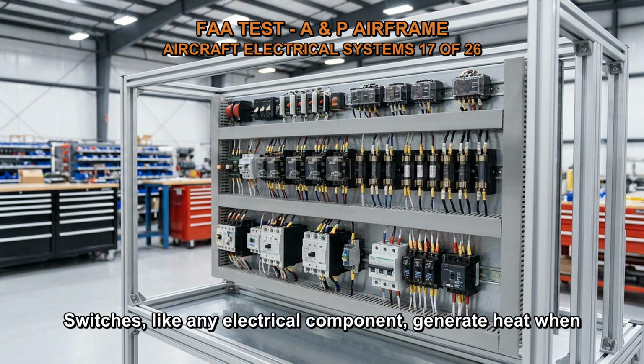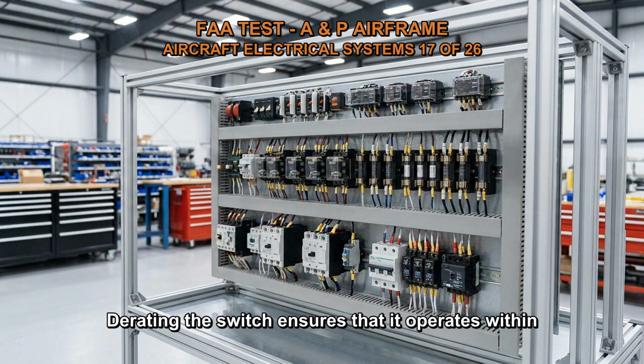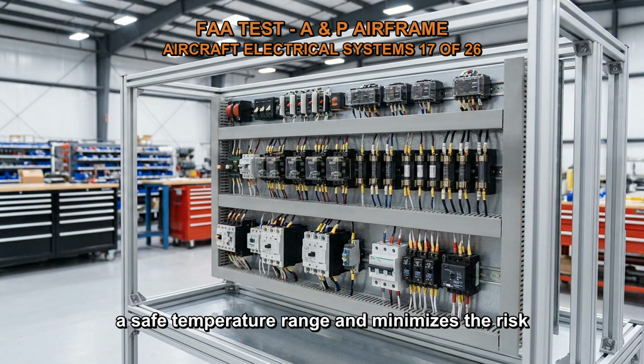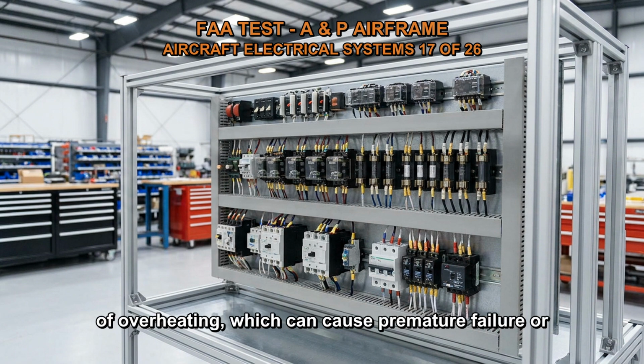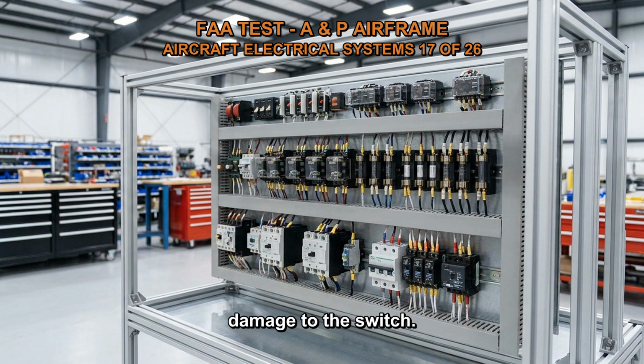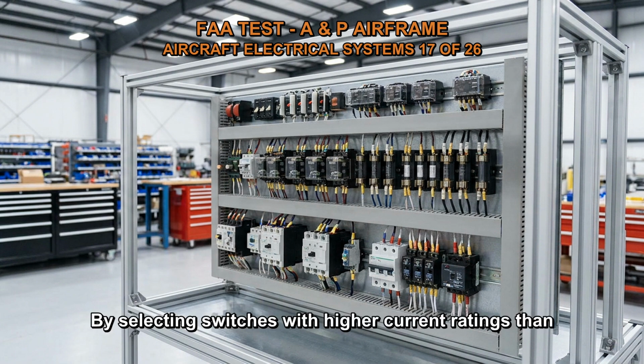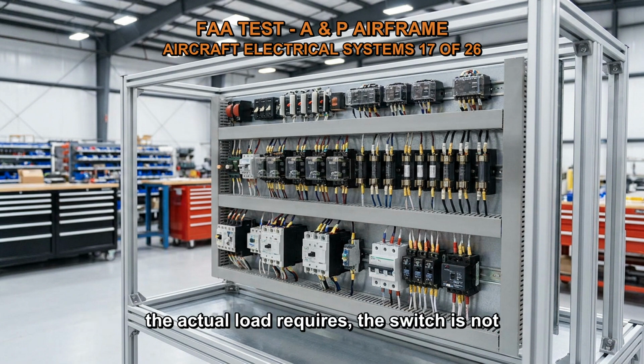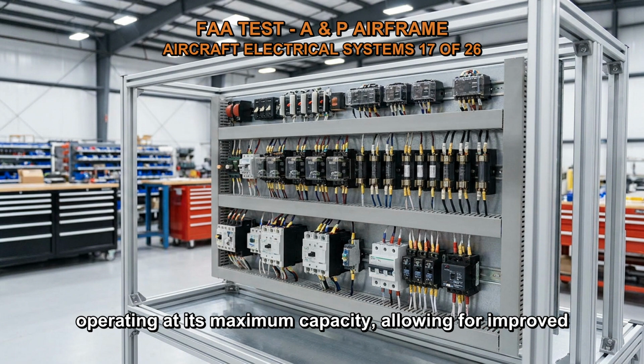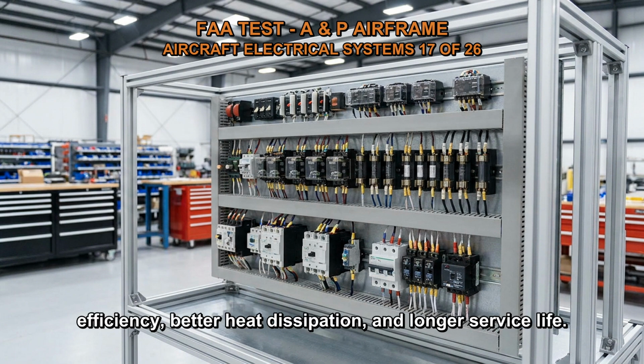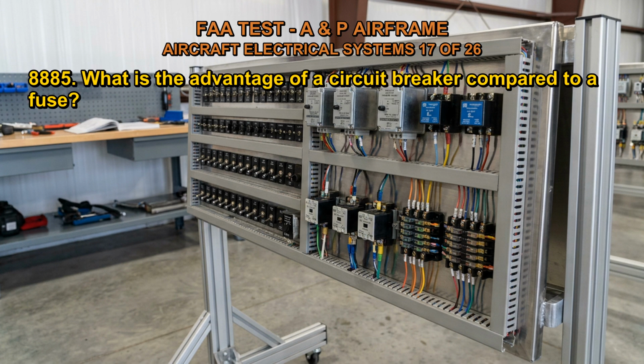Switches, like any electrical component, generate heat when current flows through them. Derating the switch ensures that it operates within a safe temperature range and minimizes the risk of overheating, which can cause premature failure or damage to the switch. By selecting switches with higher current ratings than the actual load requires, the switch is not operating at its maximum capacity, allowing for improved efficiency, better heat dissipation, and longer service life.